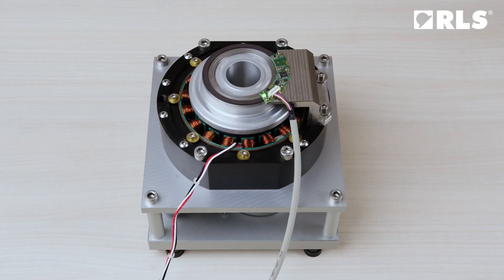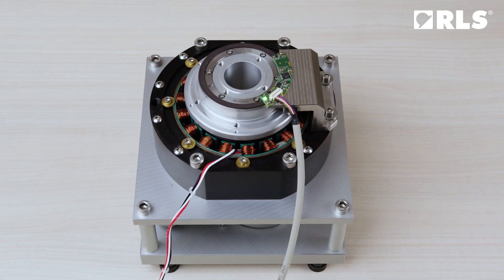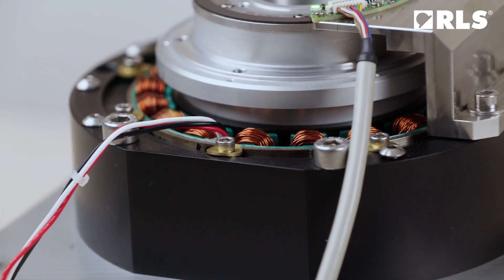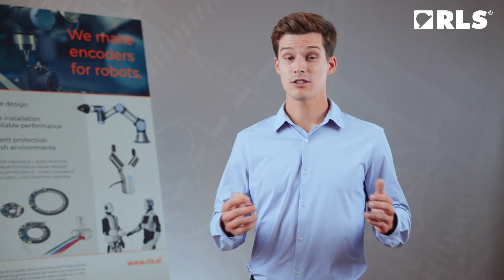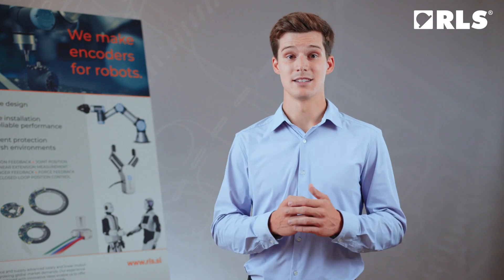This multipole brushless motor is a typical example of a closed-loop application where an AksIM encoder is used as a single feedback device to provide positioning, speed and commutation of a motor. Such a solution eliminates the need for hall sensors and an incremental encoder, significantly reducing the number of wires and simplifying installation and configuration.